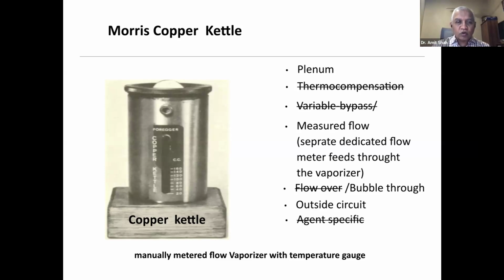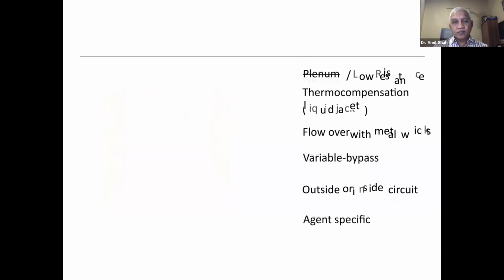It was again a bubble-through, so the gas will pass through the liquid and takes maximum concentration. It can be used on the anesthesia machine, but cannot be used in the field outside the OR. So here you have to put a separate flow which passes through this copper kettle, which was heated.